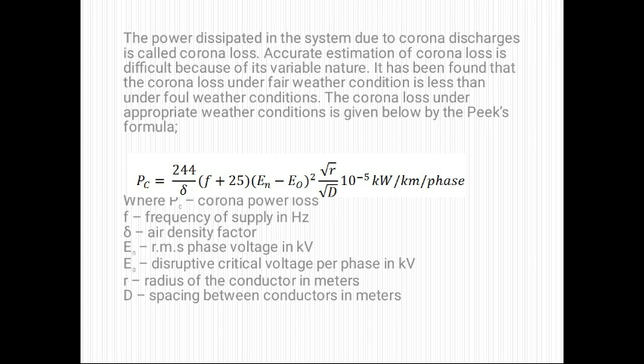where Pc is corona power loss, f is the frequency of the supply, delta is the air density factor, E is the RMS phase voltage in kilovolt, E0 is the disruptive critical voltage per phase in kilovolt, r is the radius of the conductor in meter, and d is the spacing between the conductors in meter. These are the factors which affect corona.